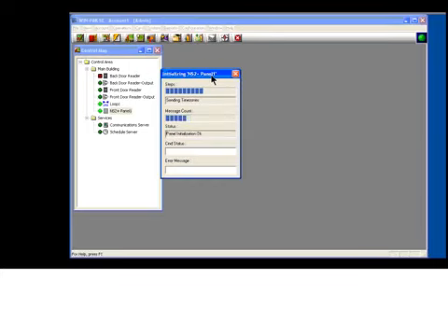At this point, your software does function. If somebody were to have a card in the system and swipe a card, what will happen is the reader will read the card, pass the data to the panel, and the panel will say, hey, you know what, you're not in my database. But then it'll ask the software, hey, is this a valid card? If it is a valid card, it'll unlock the door and download the card. We call that host RAM. That's a built-in feature in the Winpak software.